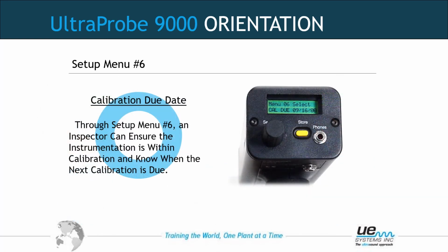Once we get back to the main setup menu, we rotate to menu number 6. This is calibration due date. This is typically 12 to 13 months from when the calibration had occurred. So this unit was due in on September 16th of 2000, which meant the unit would have been calibrated around September of 1999, a year previous. Again, this is not when it was calibrated, but when it is due in for calibration. Maintaining a well-calibrated ultrasonic unit is important for our inspections.